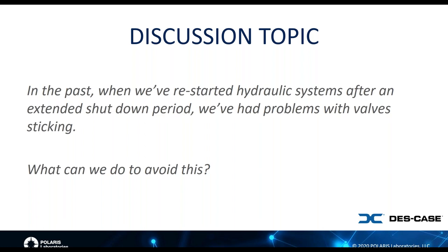Yeah, thanks, Barb. One of the things that we find with hydraulic systems is the fluid over time will degrade as an oil is stressed through heat, and in particular in hydraulic systems, we see a lot of compressive heating. And of course, when we heat oil, we induce oxidation, and that oxidation starts to degrade the fluid. When a hydraulic fluid oxidizes, the byproducts of that are sticky or resinous in nature. You may have heard the term varnish used to describe that a little bit.